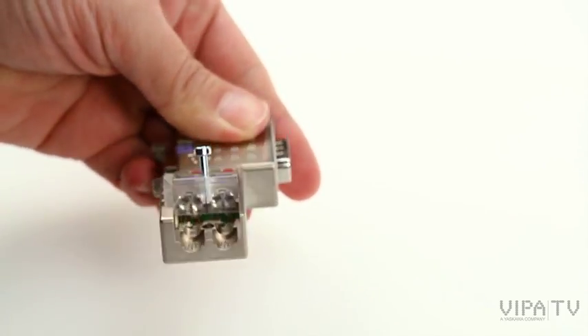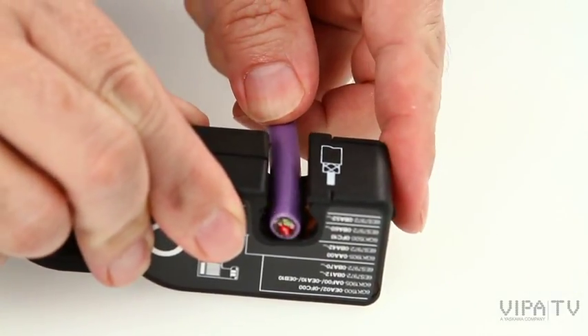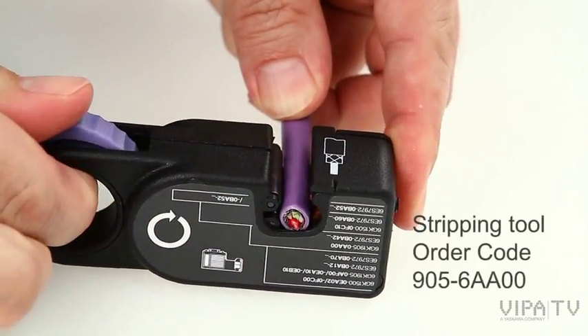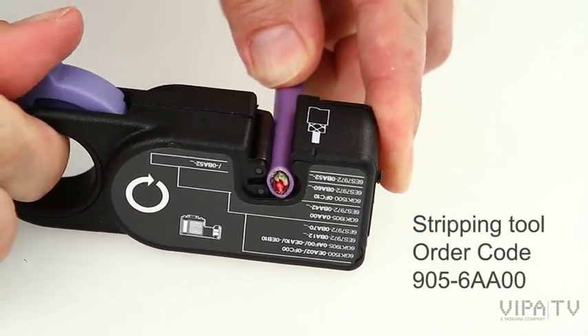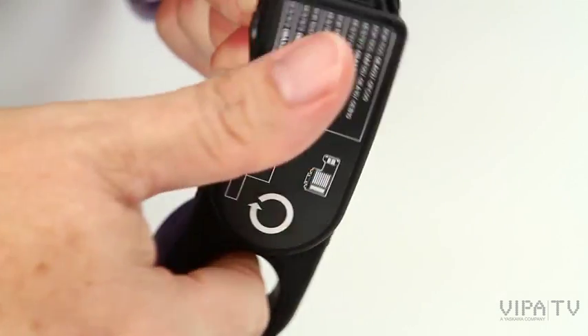Insert a flexible or rigid Profibus cable into the stripping tool and tighten it. Turn the stripping tool several times until notches are produced—a deeper one on the front and a lighter one on the rear of the cable.